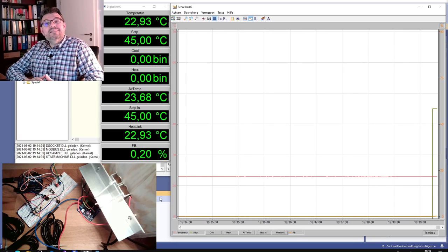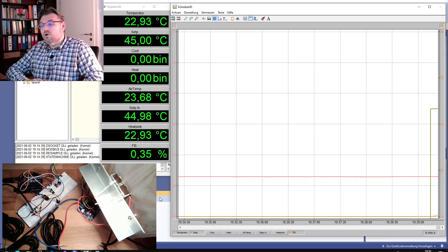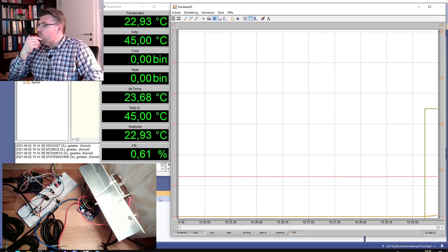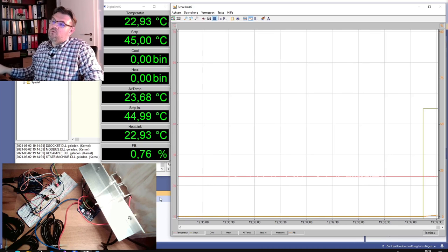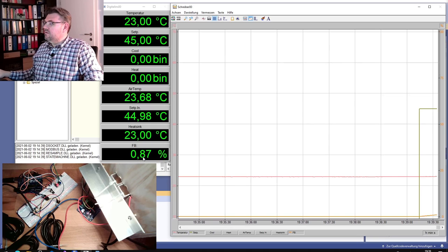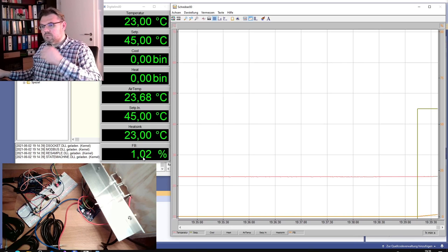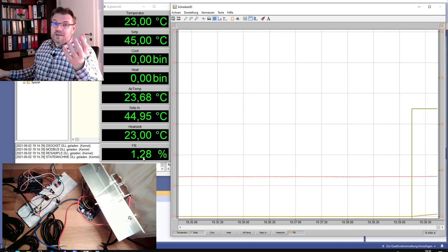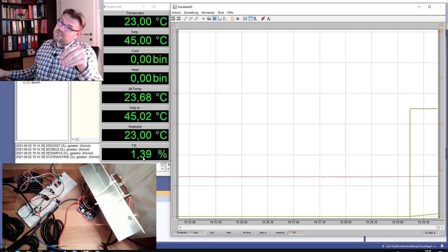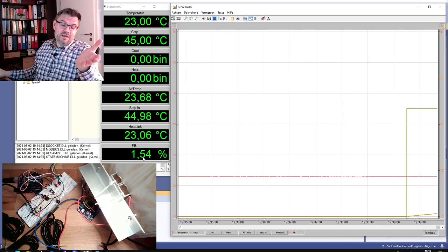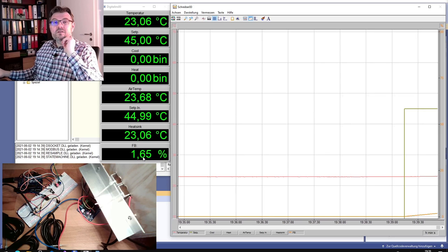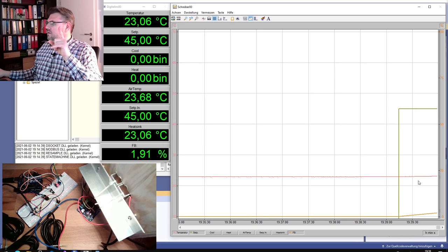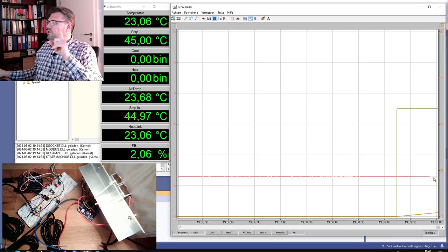And we see, since I've changed this to slower speed, also the rise is really slow now, compared to what we've seen before. Right now, we only have 1% of the output. So it's reacting slower at the beginning, that's for sure. This is actually what is good for us, because if it's reacting slower, we would have time to break. So we're not accelerating too fast. But you see, it's already reacting. It seems like the temperature is already rising.